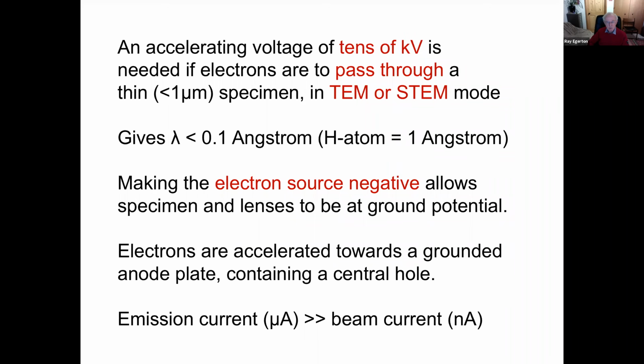Now, in general, this kind of equipment has the lens column and the specimen at ground potential. And that has the obvious advantage in terms of convenience and safety that most of the equipment is at ground potential. That means the electron source is at a high negative potential. Usually it's at the top of the instrument, and so the high potential is up at the top, away from where the operator sits. And the electrons are accelerated from this negative potential up to ground potential.